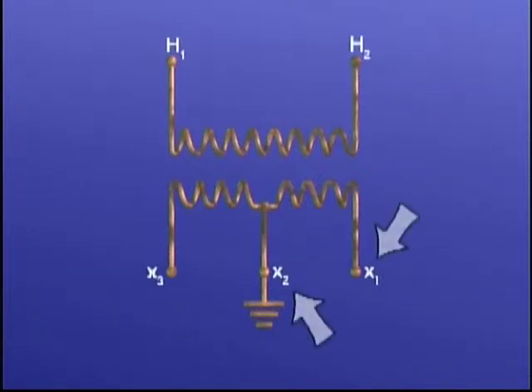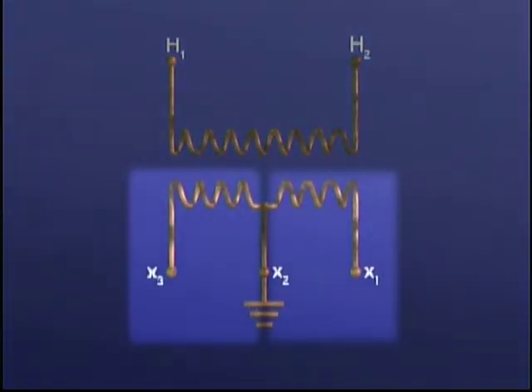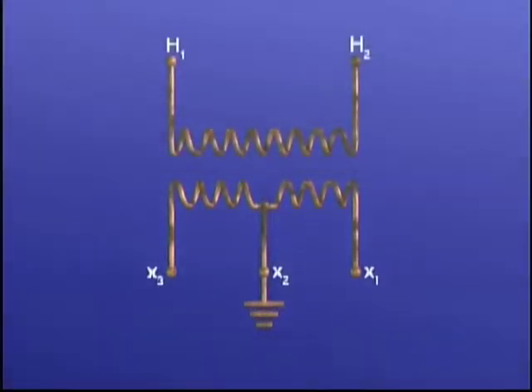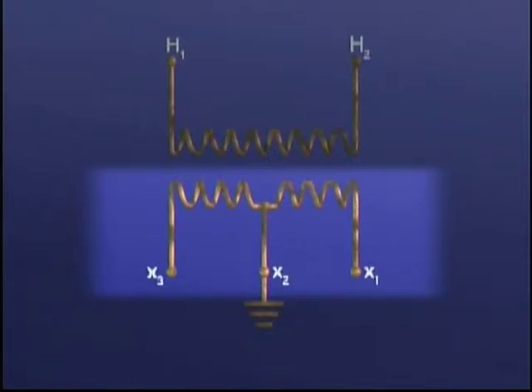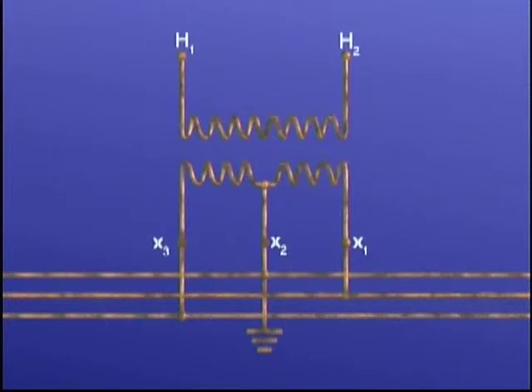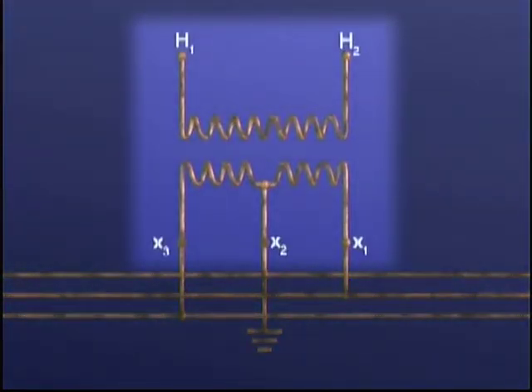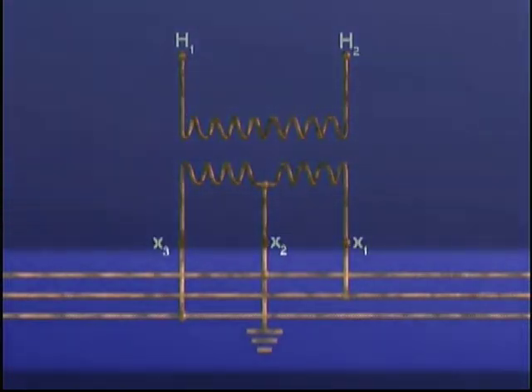120 volts can be supplied by connections to the X1 and X2 bushings or by connections to the X2 and X3 bushings. In both cases, the ground on the X2 bushing splits the secondary winding into two equal coils, each capable of supplying 120 volts. The secondary winding can also supply 240 volts. This is accomplished by connections between the X1 and X3 bushings. With this in mind, we can begin to see what the secondary bus supplied by this single-phase transformer will look like. It will consist of three wires.